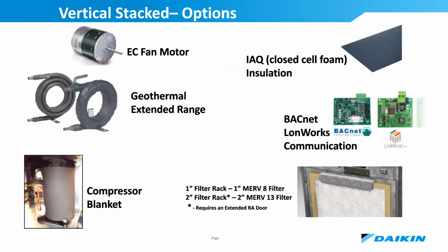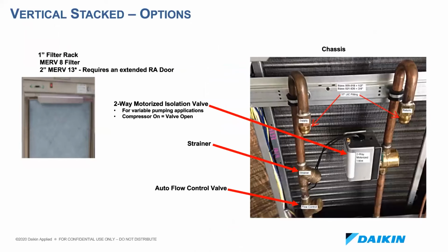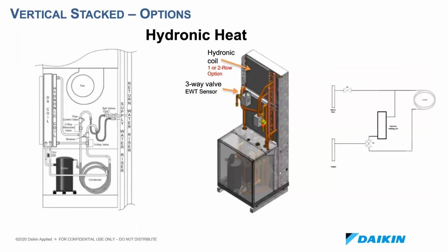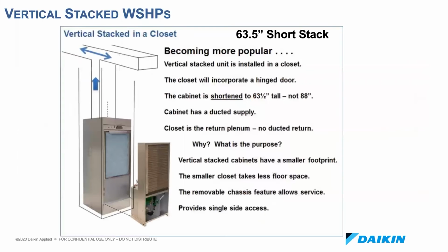Some of the factory options include the EC fan motor, closed cell foam insulation, geothermal for extended range applications, compressor sound blankets, a BACnet or LonWorks communication card, and different filter options. We also offer different factory installed piping packages that include a Y strainer, a flow control valve, and a 2-way motorized valve for variable pumping applications. We have a hydronic heating option available for hybrid applications.